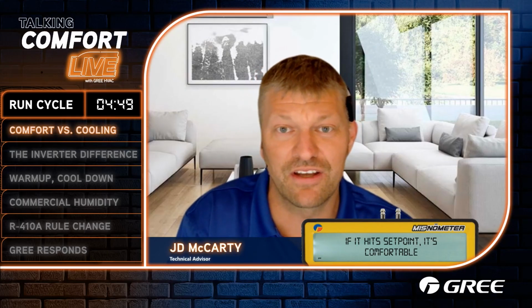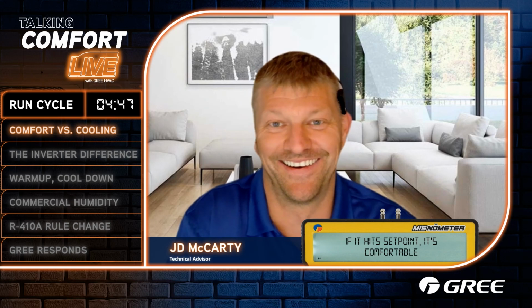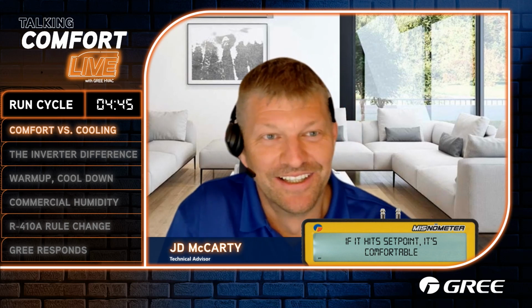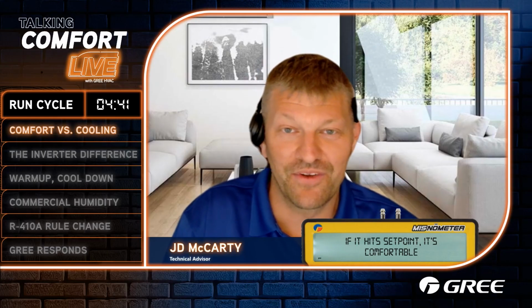And I told him, well, it doesn't have time to remove that humidity. It's way oversized. It's a whole ton oversized. So it is a prime example of exactly what we're talking about. And of course it was meeting that temperature. They turned it down even to 70, 68, and they're like, we can't get that humidity out of here. They thought it was a defective unit. He said, I was getting ready to rip this unit out of here. So yeah, I was like, this is going to go good with what we're talking about later today. I'm going to use this.